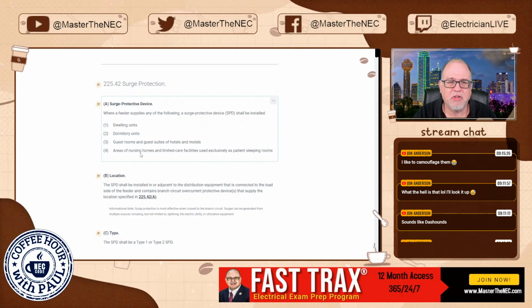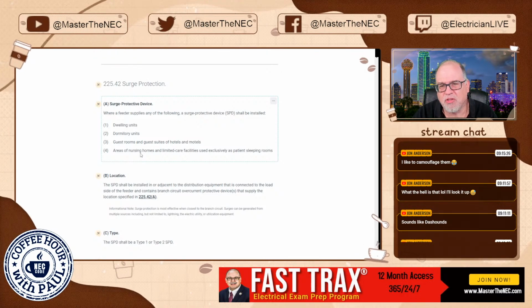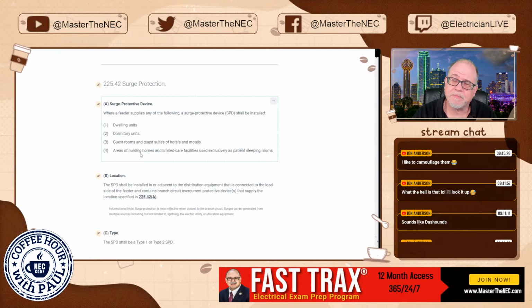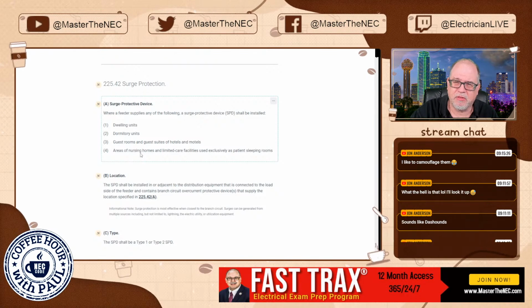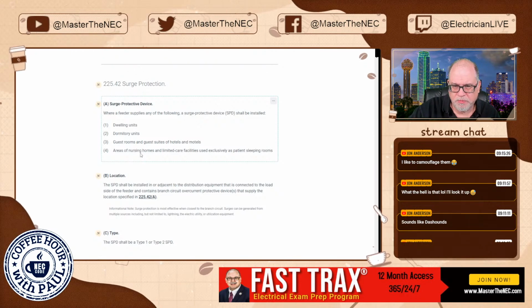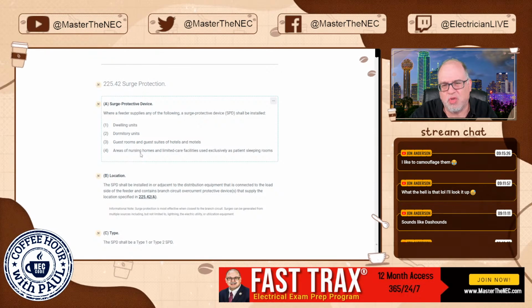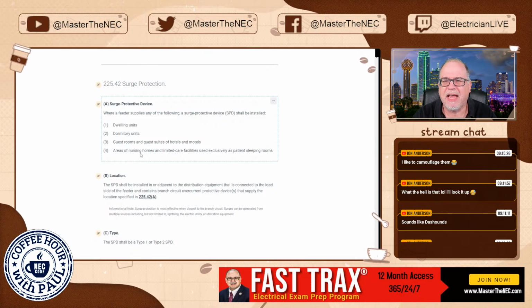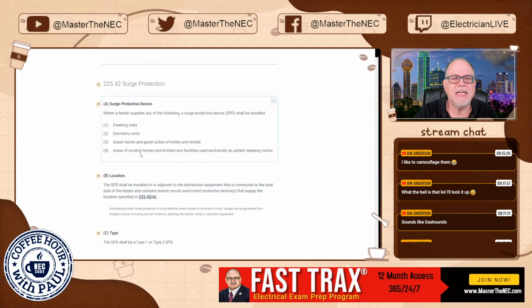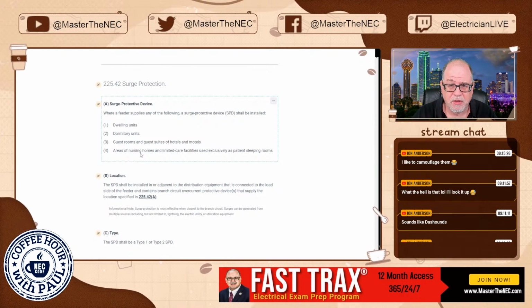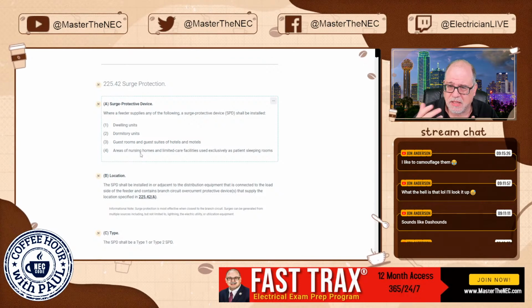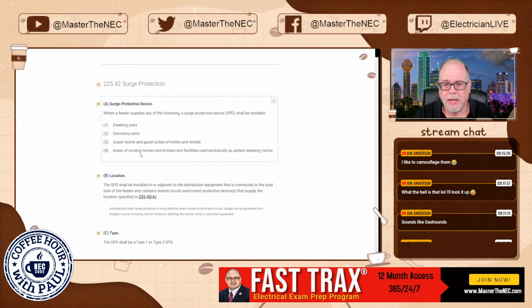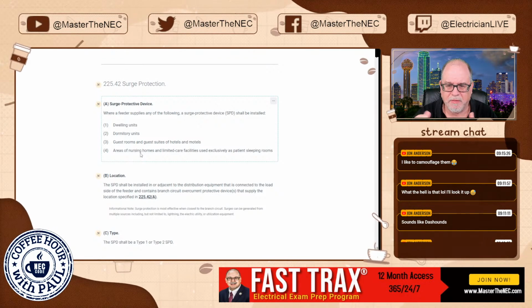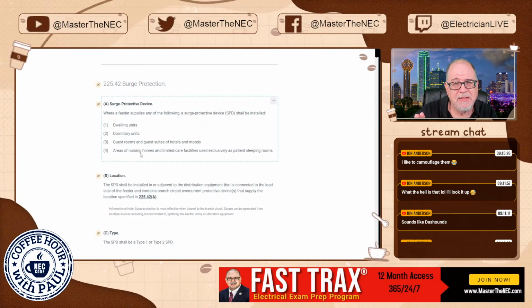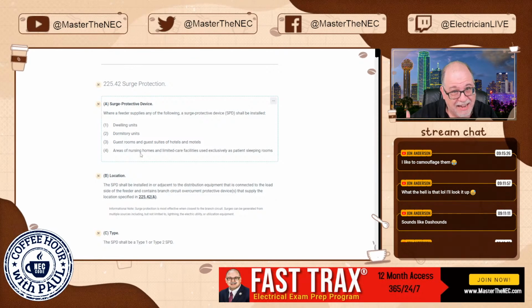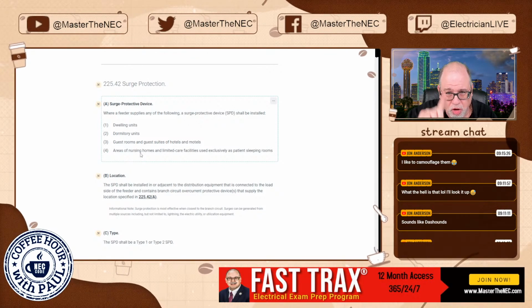So this is going to mean that you are going to have to add surge protection. Let's think about this. If I have an apartment complex and I have individual feeders that are supplying each one of these dwelling units, I am now going to have surge protection for each one of those dwelling units. The good news is they have the ones that plug right onto the bus. And we're going to see about the location and all that kind of stuff. But again, it's pretty easy to achieve. The fact is you're going to have to add them now, so make sure you put that in your cost, all right?